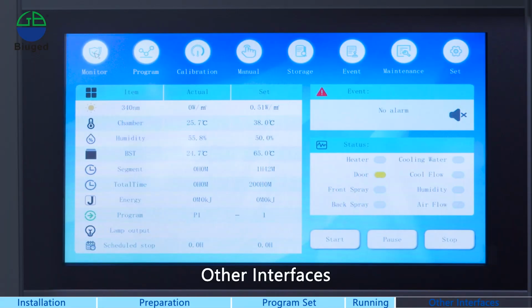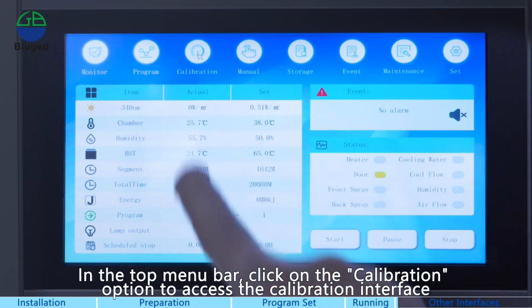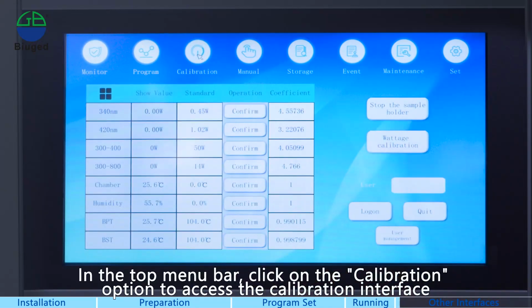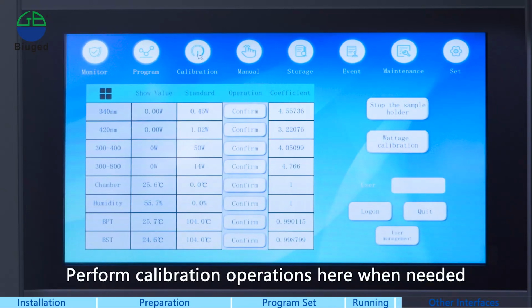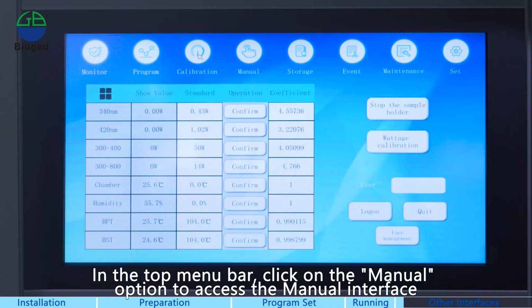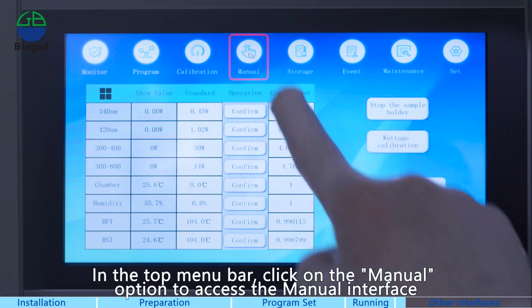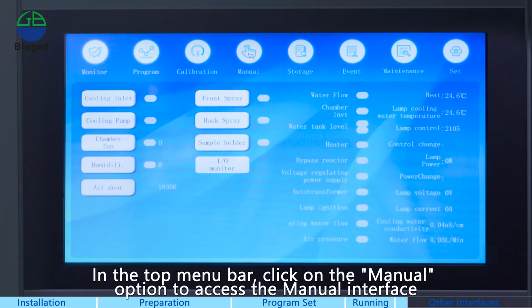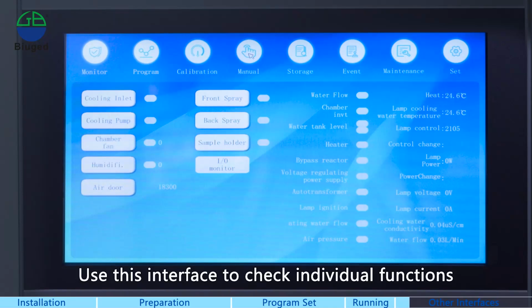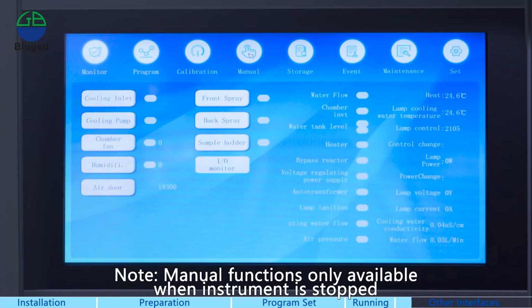Other interfaces. In the top menu bar, click on the Calibration option to access the calibration interface. Perform calibration operations here when needed. In the top menu bar, click on the Manual option to access the manual interface. Use this interface to check individual functions. Note, manual functions only available when instrument is stopped.